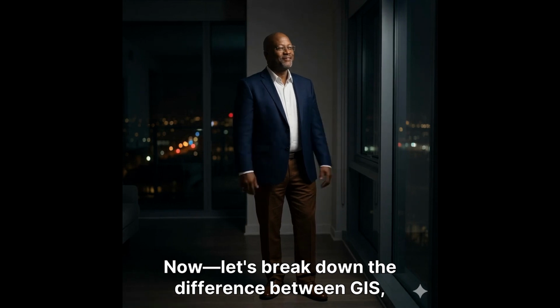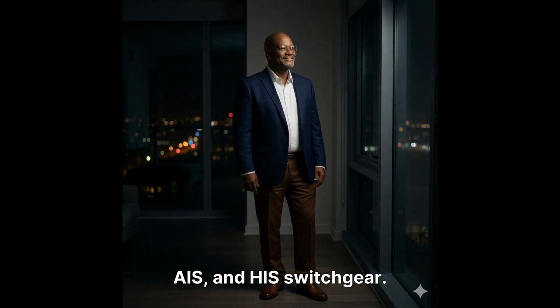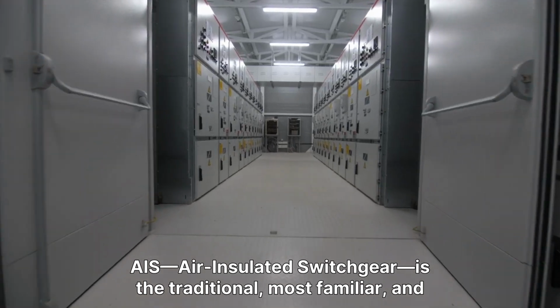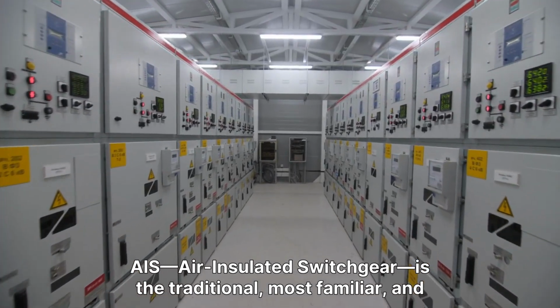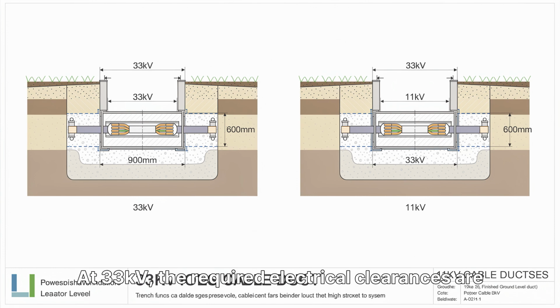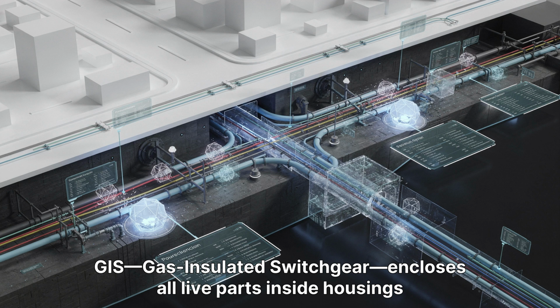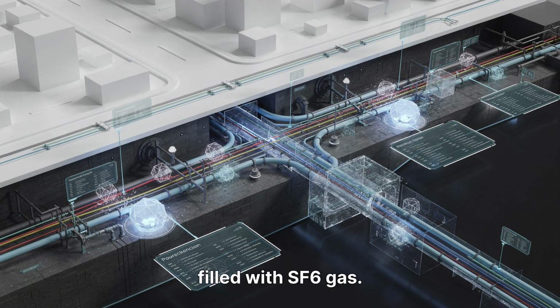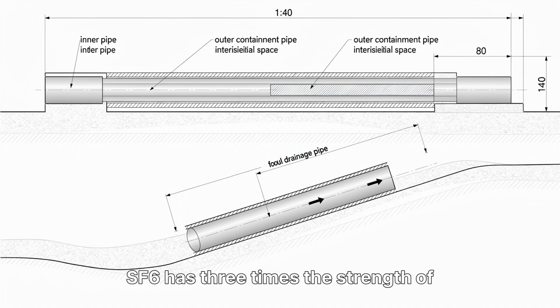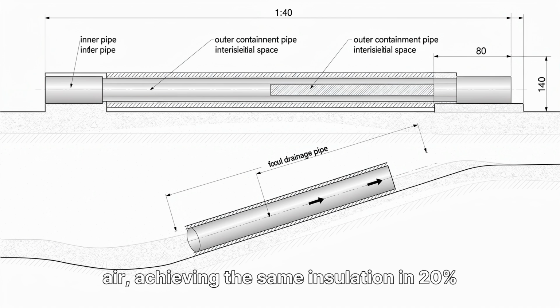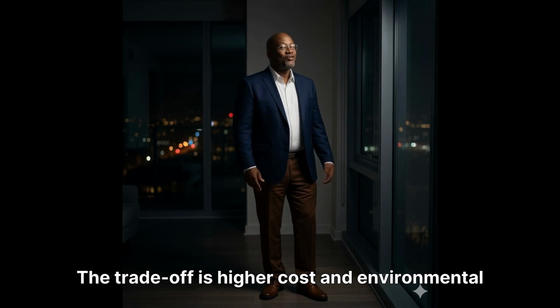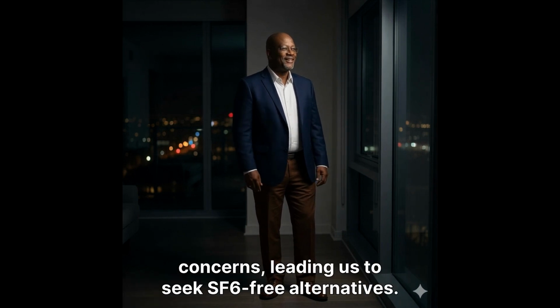Now, let's break down the difference between GIS, AIS, and HIS switchgear. AIS, air-insulated switchgear, is the traditional, most familiar and lowest cost option. Its limitation is footprint. At 33 kV, the required electrical clearances are significant. GIS, gas-insulated switchgear, encloses all live parts inside housings filled with SF6 gas. SF6 has 3 times the strength of air, achieving the same insulation in 20% of the space. The trade-off is higher cost and environmental concerns, leading us to seek SF6-free alternatives.